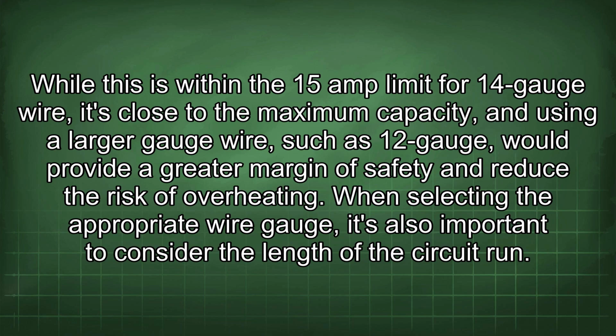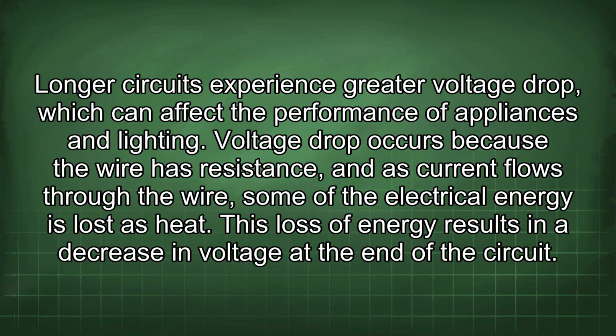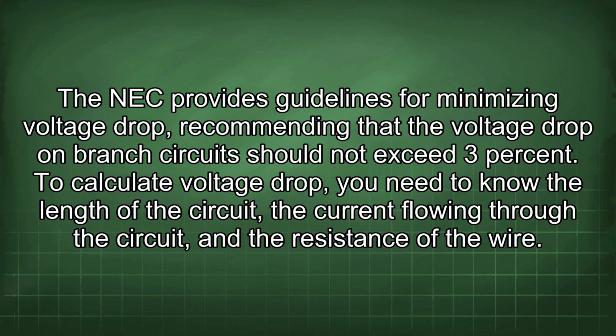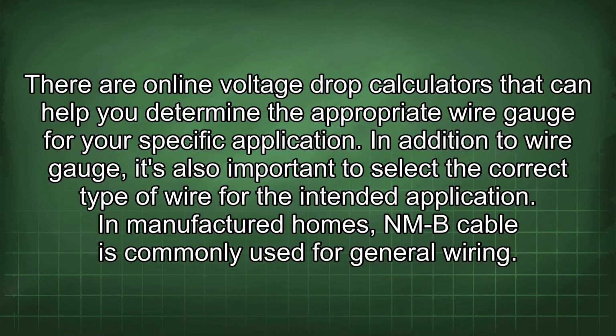When selecting the appropriate wire gauge, it's also important to consider the length of the circuit run. Longer circuits experience greater voltage drop, which can affect the performance of appliances and lighting. Voltage drop occurs because the wire has resistance, and as current flows through the wire, some of the electrical energy is lost as heat. This loss of energy results in a decrease in voltage at the end of the circuit. The NEC provides guidelines for minimizing voltage drop, recommending that the voltage drop on branch circuits should not exceed 3%. To calculate voltage drop, you need to know the length of the circuit, the current flowing through the circuit, and the resistance of the wire. There are online voltage drop calculators that can help you determine the appropriate wire gauge for your specific application.